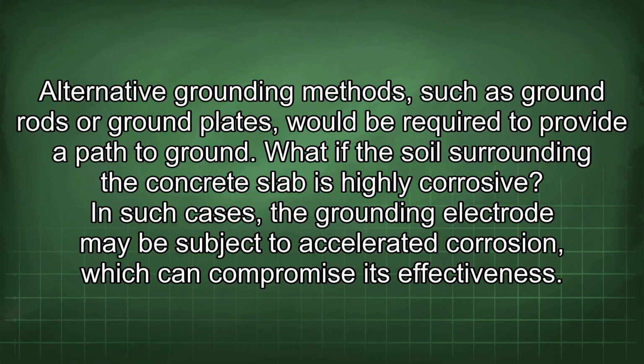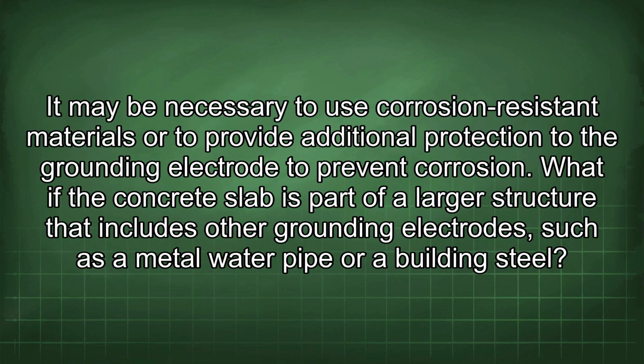What if the soil surrounding the concrete slab is highly corrosive? In such cases, the grounding electrode may be subject to accelerated corrosion, which can compromise its effectiveness. It may be necessary to use corrosion-resistant materials or to provide additional protection to the grounding electrode to prevent corrosion.